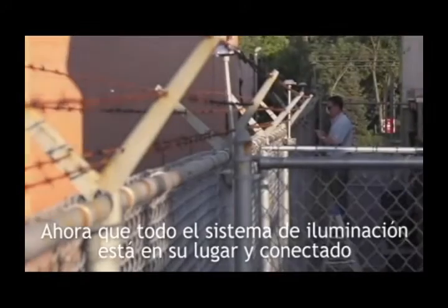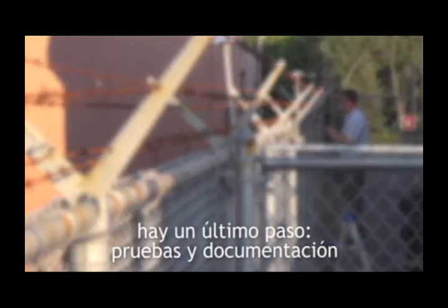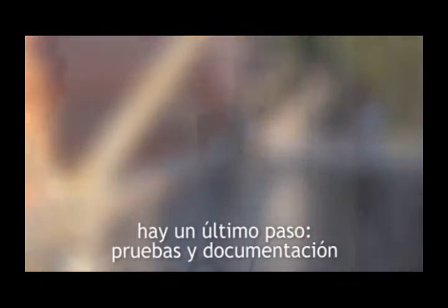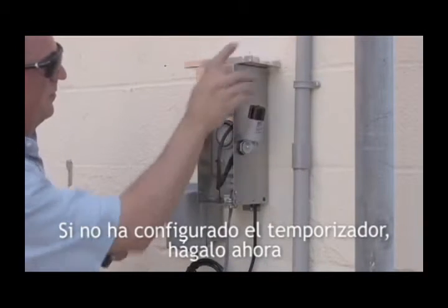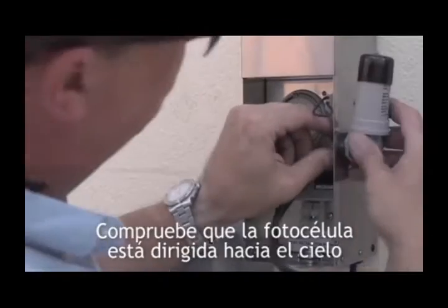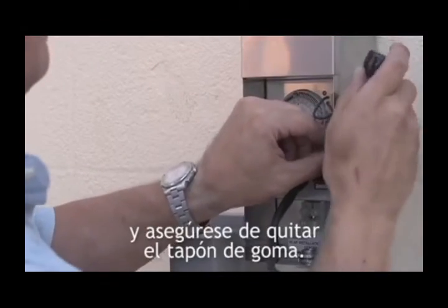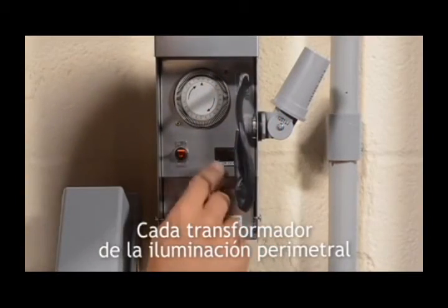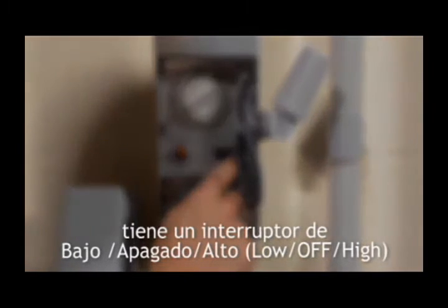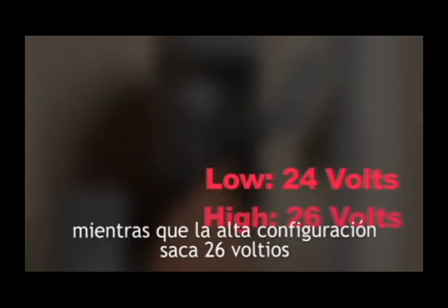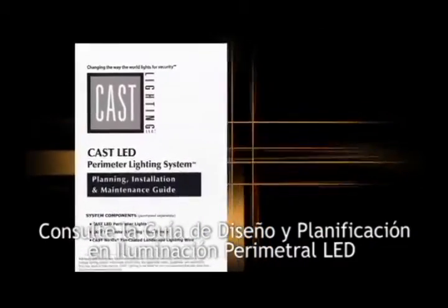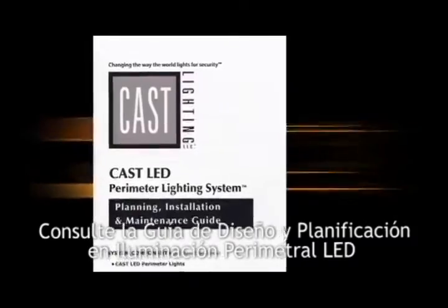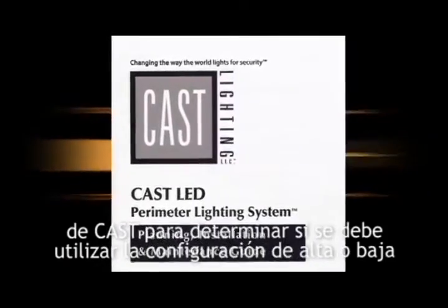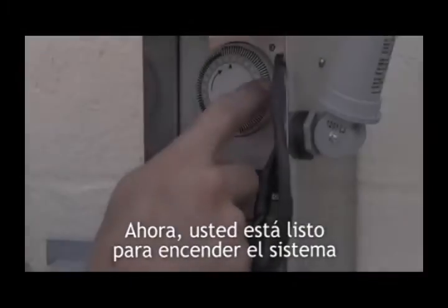Now that the entire lighting system is in place and connected, there's one final step: testing and documentation. If you haven't already set your timer, do so now. Check that your photocell is aimed to the sky and be sure to remove its rubber cap. Every perimeter lighting transformer has a low, off, high switch. The low setting sets the output at 24 volts, while the high setting puts out 26 volts. Refer to the Cast LED Perimeter Lighting Planning and Design Guide to determine whether to use the high or low setting. Now you're ready to turn on the system.